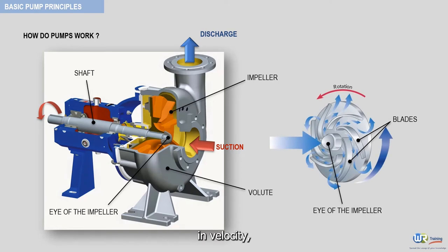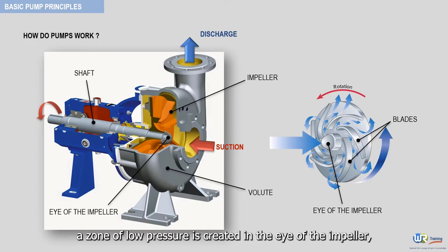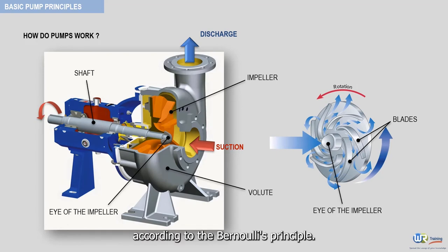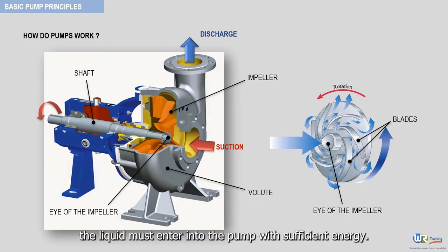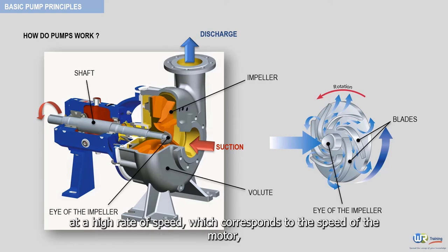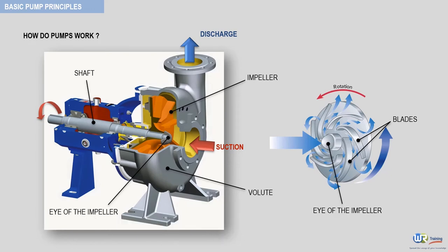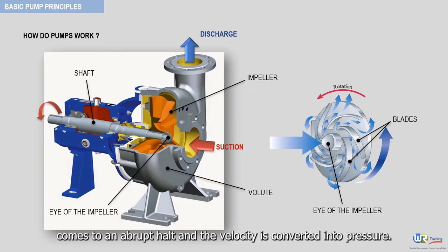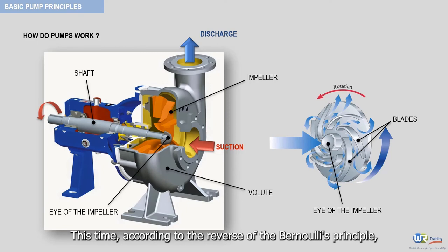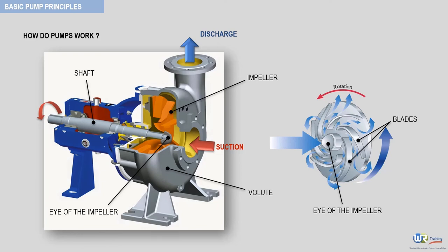As the fluid accelerates in velocity, a zone of low pressure is created in the eye of the impeller, according to Bernoulli's principle — as velocity goes up, pressure goes down. This is another reason the liquid must enter into the pump with sufficient energy. The liquid then leaves the outside diameter of the impeller at a high rate of speed, corresponding to the speed of the motor, and immediately slams into the internal casing wall of the volute. At this point, the liquid's centrifugal velocity comes to an abrupt halt and the velocity is converted into pressure.